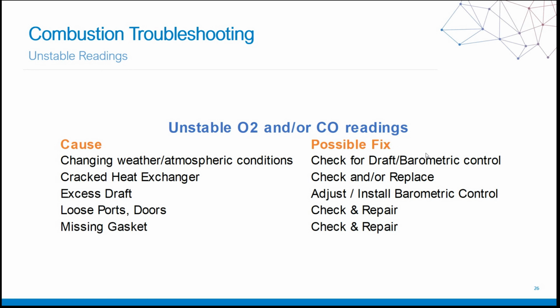Excess draft: again, we want to adjust and check the barometric control to make sure that it is functioning properly. Loose ports and doors and missing gaskets are rudimentary things. When you first evaluate a system, those should be your usual suspects. You want to make sure that the people who touched the system before you put the doors back on properly, that the gaskets were put on properly, that they're not falling off, or that they're not compromised and need to be replaced. Those are simple things to look out for and account for before you get into more involved troubleshooting.